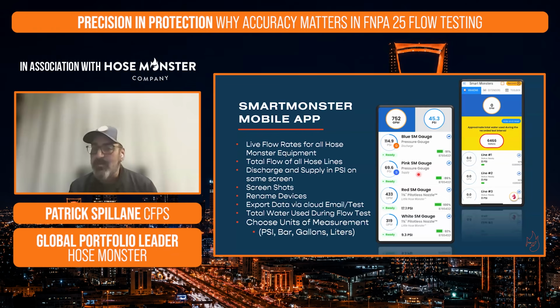So here we don't have to do any math in the middle of our test, right? We're going to have our discharge pressure minus our suction pressure, and that's going to show live up in the corner as we're doing our fire pump test. We can take screenshots. There's a screenshot button up in the top right corner. That's going to save your entire screen. So if you have multiple Hose Monster devices and not all of them fit on the screen, when you take that screenshot, it's going to take a picture of any of those devices even lower down on the screen, so you don't have to scroll up and down to take multiple photos.